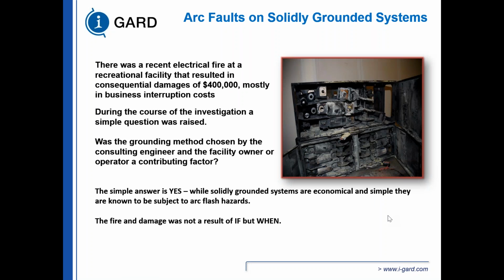Here's an example of a solidly grounded system where they had an intermittent arcing fault. This was on a 600 volt system at a commercial facility. The owners believed that they were trying to economize the installation by putting in fuse switches, and because of a ground fault that occurred, the entire facility was down for several weeks, and then they had to put in backup generation to keep the facility going again.